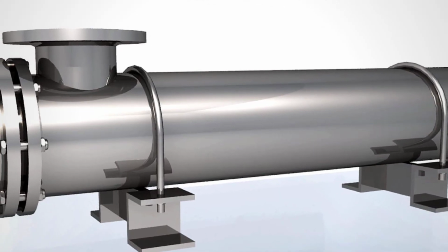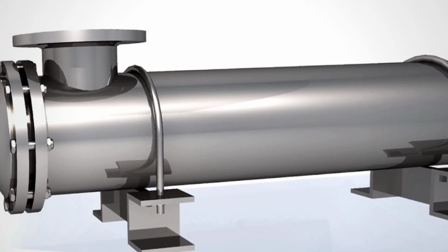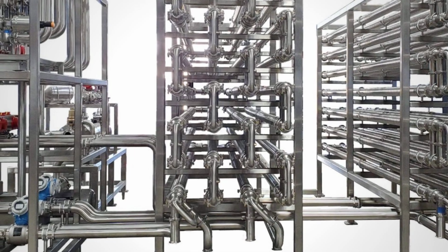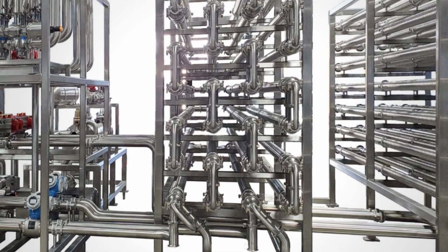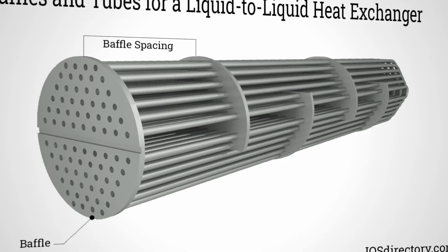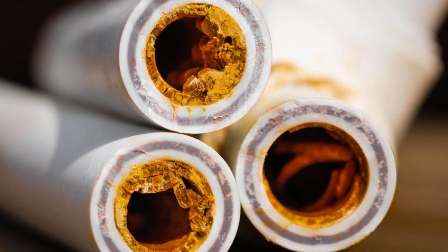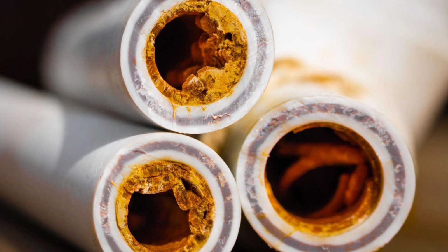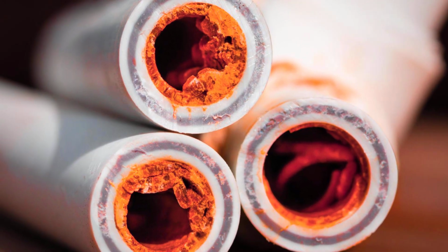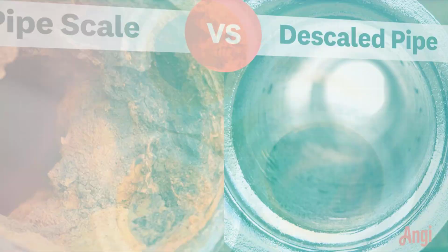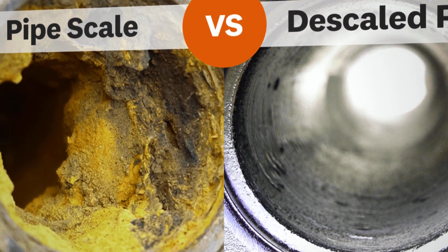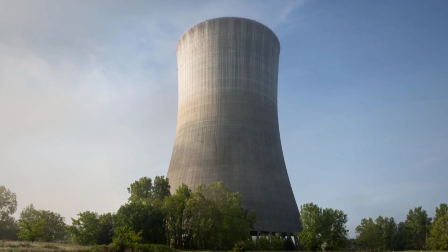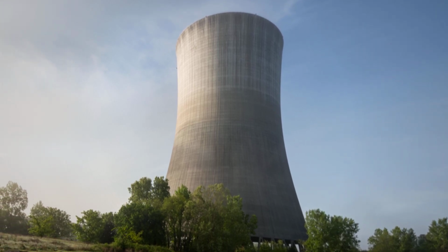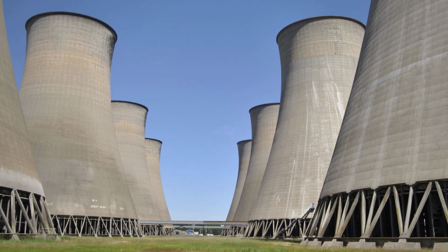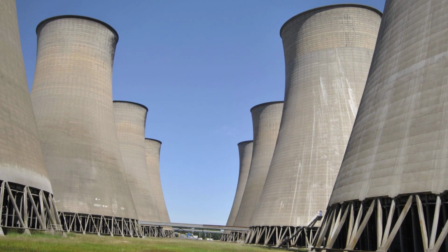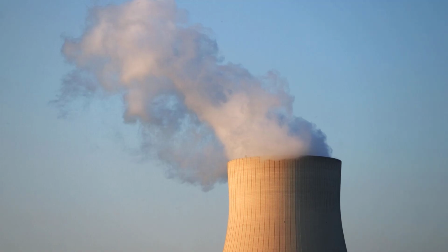Furthermore, not all cooling towers use evaporative methods. Dry cooling towers incorporate internal heat exchangers, with the cooling water flowing in a closed loop. In dry systems, cooling is limited by the higher dry bulb temperature rather than the wet bulb, but there is no water loss due to evaporation, and the buildup of minerals, common in wet systems as cooling water evaporates, is avoided. The prevalence of large natural draft towers at power plants is fundamentally linked to scale.